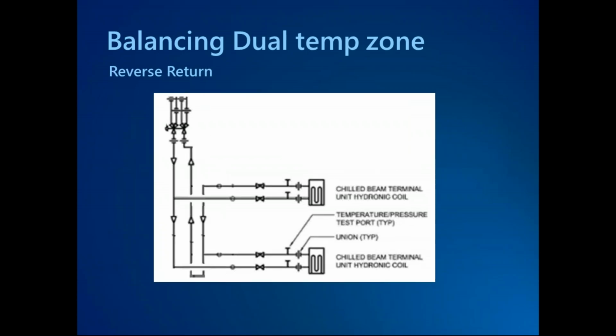The other solution is, again, reverse return piping. You can use reverse return piping for the dual temperature zone. It is adding more piping, which is one of the things we're trying to get away from. So it's a cost analysis that needs to be done, whether it makes more sense to do the reverse return piping or to include manual balancing valves. For the most part, we're seeing manual balancing valves still being used in the market as of today.